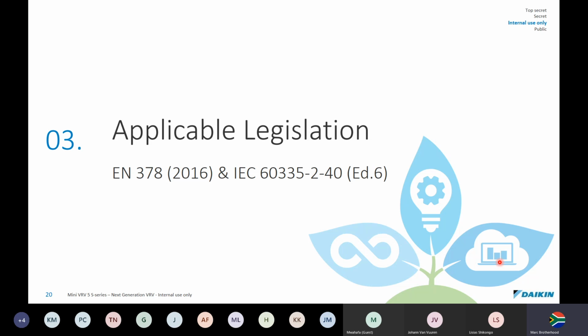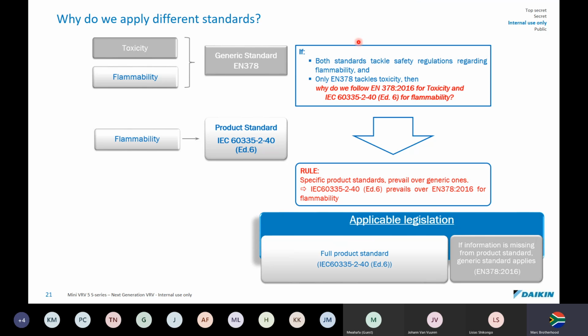When you develop these systems and they have a refrigerant that is flammable, you have to apply to legislation. So Daikin chose to use two different standards. I'm not going to bore you guys too much with this, but there's a generic standard, which is EN, the European Standard, EN 378. In this standard, if you open this book, it talks about toxicity, which is how poisonous a gas is, and it also talks about how flammable a gas is. So both standards tackle safety regulations. But what Daikin decided to do for flammability was to rather use another standard, which is the IEC 60335. The reason they used this standard is because it's a lot stricter. It's got more rules in it, and Daikin chose a more difficult standard to comply with, with a lot more stringent rules.